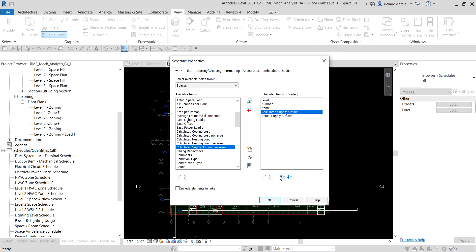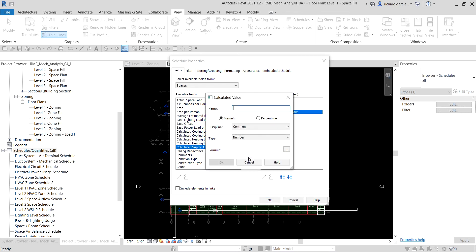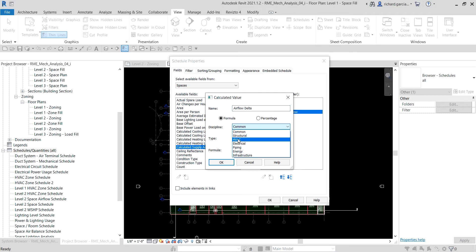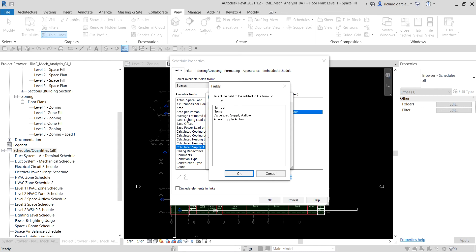Now let's define the airflow delta formula. Click Add Calculated Parameter — this icon — which opens the Calculated Value dialog. For the name I'll put 'Air Flow Delta'. We'll use a formula for the HVAC discipline, so I select HVAC, and the type is Airflow. To build the formula I click the ellipsis button, then select Calculated Supply Air Flow and click OK.